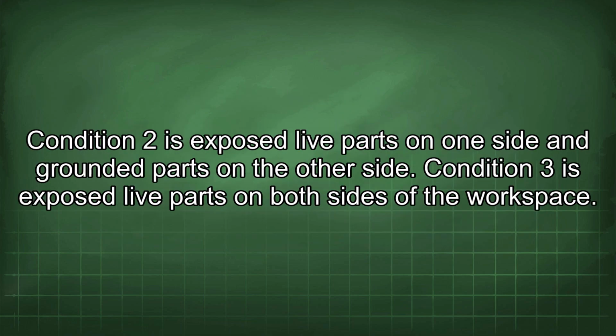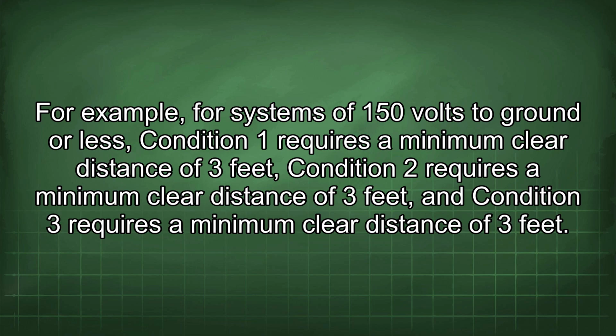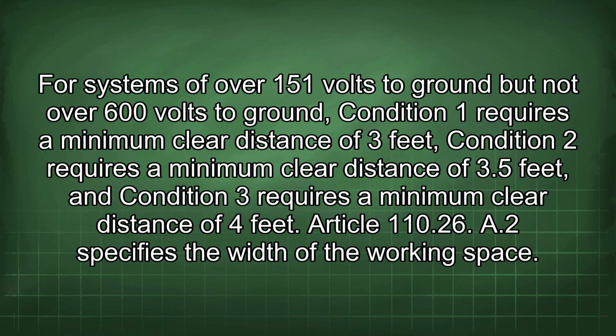Condition 2 is exposed live parts on one side and grounded parts on the other side. Condition 3 is exposed live parts on both sides of the workspace. For example, for systems of 150 volts to ground or less, Condition 1 requires a minimum clear distance of 3 feet, Condition 2 requires a minimum clear distance of 3 feet, and Condition 3 requires a minimum clear distance of 3 feet. For systems of over 151 volts to ground, but not over 600 volts to ground, Condition 1 requires a minimum clear distance of 3 feet, Condition 2 requires a minimum clear distance of 3.5 feet, and Condition 3 requires a minimum clear distance of 4 feet.